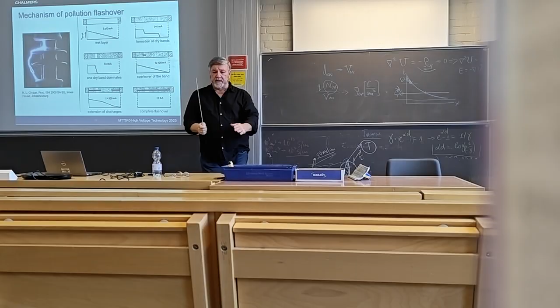Mechanism of pollution flashover. How does this happen? For the glass insulator, it's usually like that. You have the region where the insulation is, and then you have two electrodes. This is very schematic. So there is certain contamination, and this contamination is exposed to moisture, creating the path for leakage current. So it's shown here, some leakage current. Contamination is never even. At some locations there can be more salt, in another location less salt. When it's exposed to moisture, it creates this kind of semiconducting substance. So you may have regions where the concentration is lower and regions where it is higher, and then it creates what is called dry bands.